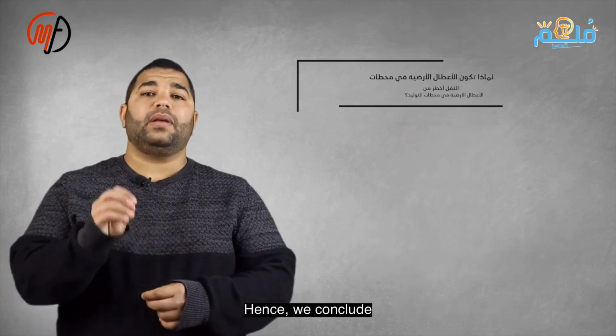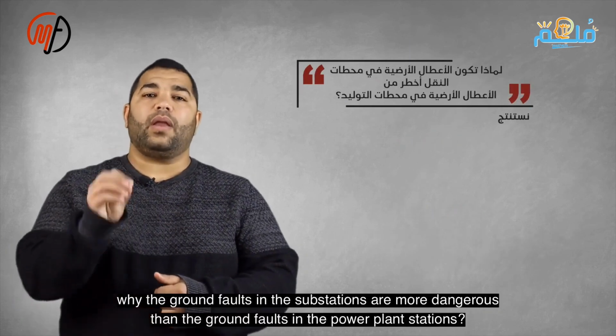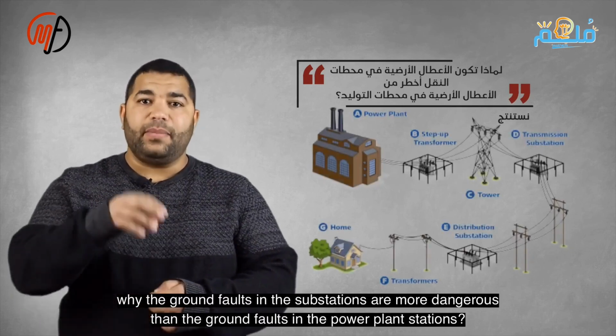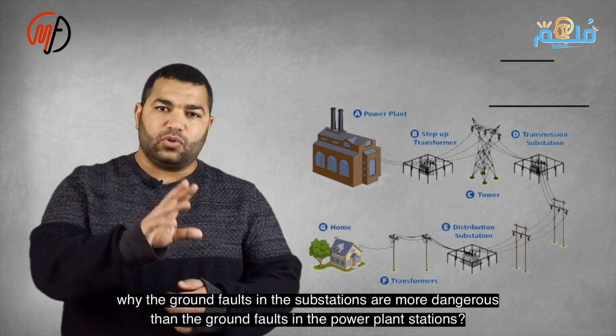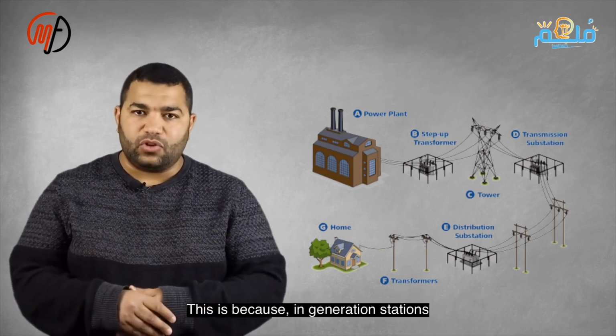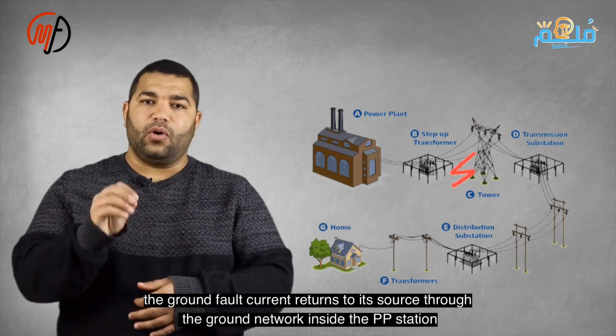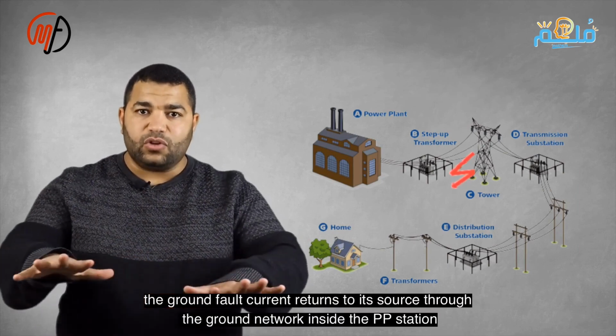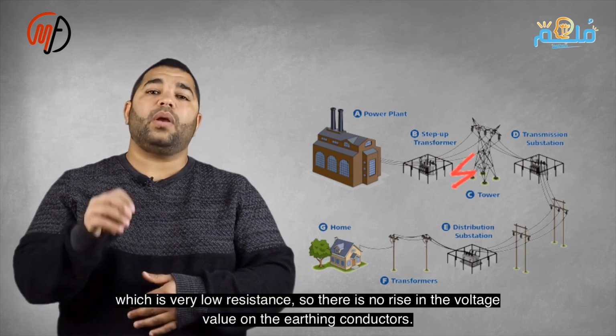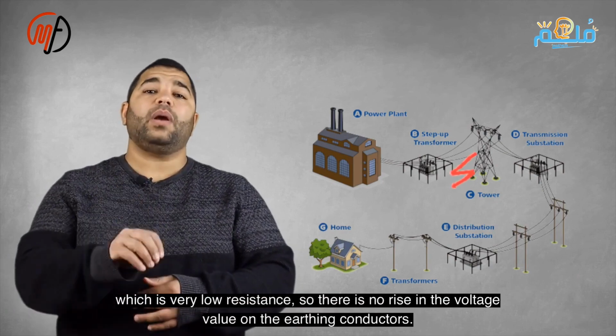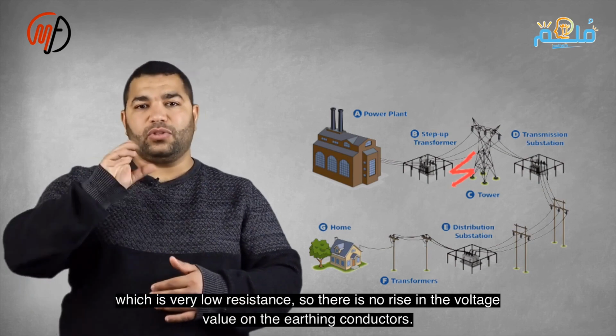In generation stations, fault current returns to its source through a low resistance grounding network. In transmission stations, fault current returns through ground resistance from outside, causing voltage rise on conductors. We need low ground resistance for most fault current to flow through it. Current has two paths, through workers' resistance or ground resistance. Lower worker resistance and higher ground resistance increase danger.